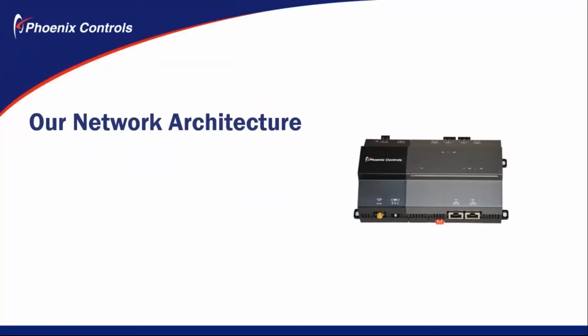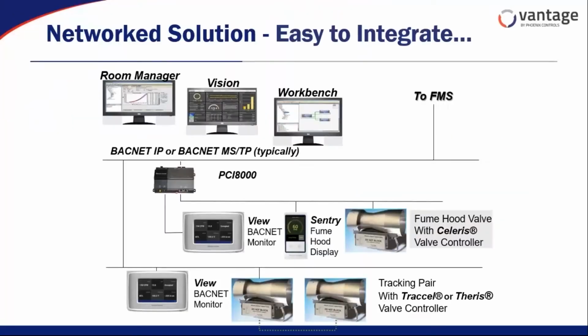Lastly, I want to talk a little bit about how the Phoenix Controls network architecture works. And this will go through a system from bottom to top, from the valve level all the way up to the building automation system.